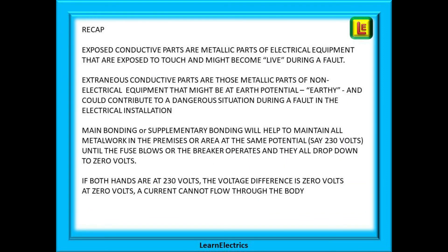A quick recap: exposed conductive parts are metallic parts of electrical equipment that are exposed to touch and might become live during a fault. Extraneous conductive parts are those metallic parts of non-electrical equipment that might be at earth potential and could contribute to a dangerous situation during a fault in the electrical installation. Main bonding or supplementary bonding will help to maintain all metalwork in the premises at the same potential — say 230 volts — until the fuse blows or the breaker operates and they all drop down to zero volts. If both hands are at 230 volts, the voltage difference is zero volts, and at zero volts a current cannot flow through the body.